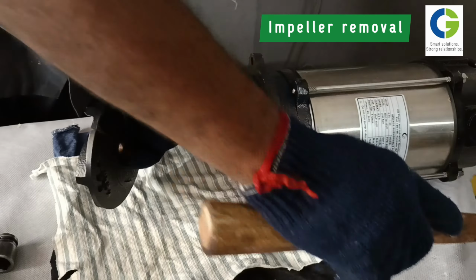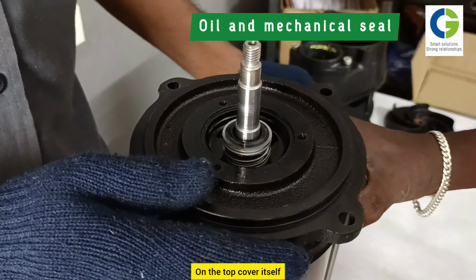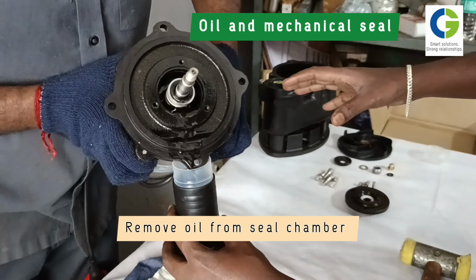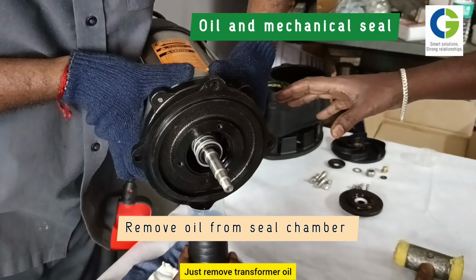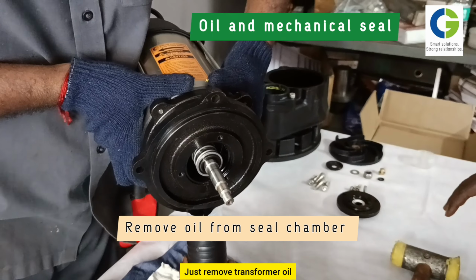After removing the top cover, you can see the mechanical seal. On the top cover itself, the oil seal is fitted. Just remove the transformer oil and throw it out. Replace it with new oil. Remove the mechanical seal. This seal is not like the standard type. It has to be mounted on both sides. One side is black ceramic, and the other side is a graphite seal.